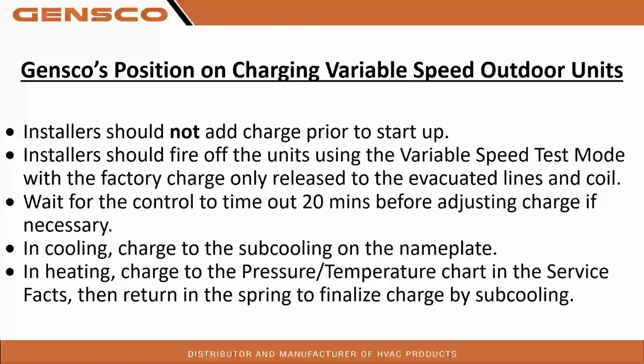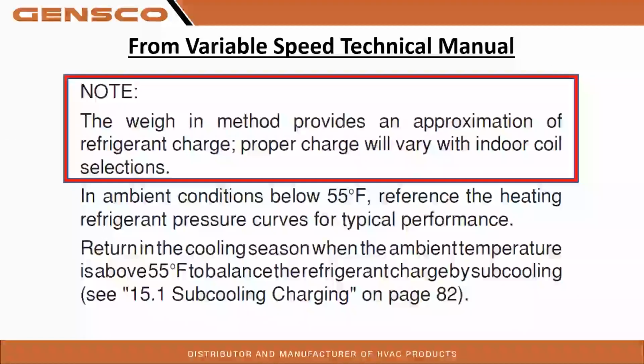We're going to release the refrigerant, and then we're going to put it in check charge mode, heating or cooling, and we're going to wait for the control to time. It's 20 minutes, and then we're going to add charge. And then in heating, we're going to use the pressure temperature chart. And that's below 55 as stated in this.